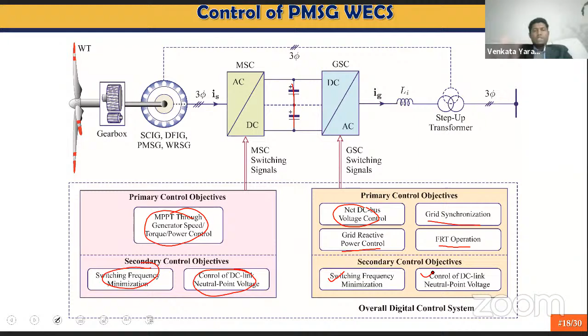On the grid side, we have more control requirements. We need to make sure that we maintain the DC link voltage at a constant value. We also need to synchronize the inverter to the grid, control the reactive power on the grid side, and perform fault ride through operation. Secondary control objectives are similar to the generator side, so we need to reduce switching frequency and also control the neutral point voltage. No matter what type of topology, we need to achieve these primary and secondary control objectives.